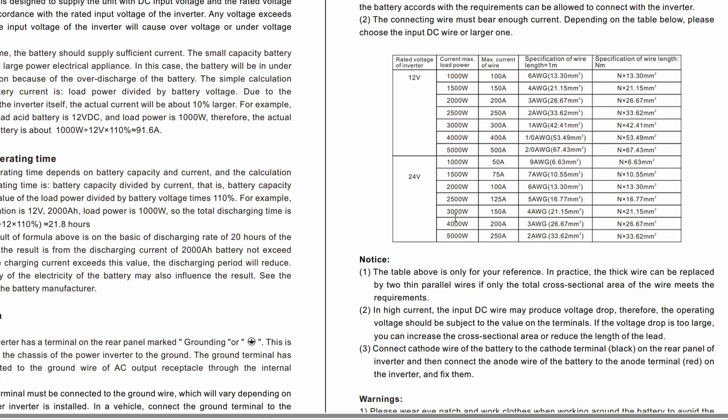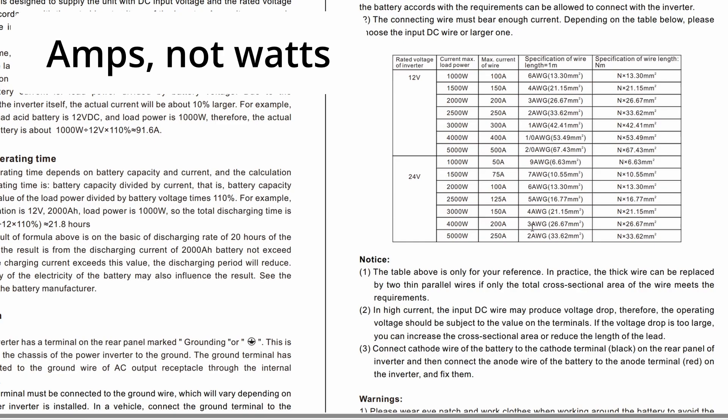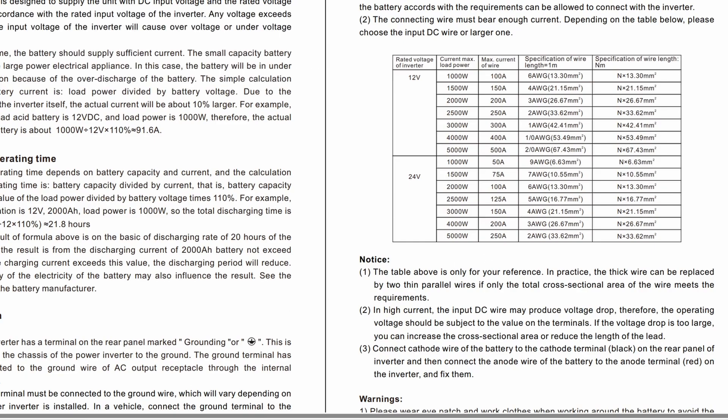If we assume that we're going to design to the maximum current that this inverter could draw, which would be the 4000 surge wattage, if we look at 4000 watts they show a max current of 200 amps but they show a wire size of 3 AWG, and 3 AWG will not carry 200 amps of power, there's no way.